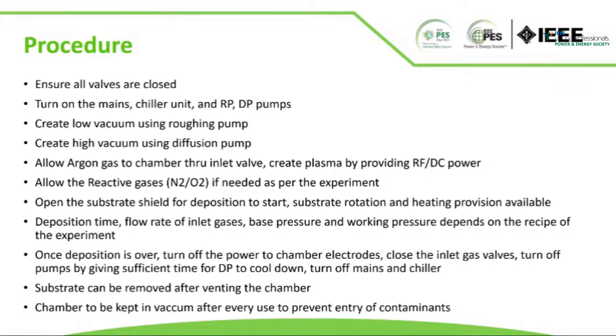Substrate rotation and heating provision is available. Deposition time, flow rate of inlet gases, base pressure and working pressure depend on the recipe of the experiment. Once deposition is over, turn off the power to the chamber electrodes, close the inlet gas valves, and turn off the pumps, giving sufficient time for the DP to cool down. Then turn off mains and chiller. The substrate can be removed after venting the chamber. The chamber is to be kept in vacuum after every use to prevent entry of contaminants.